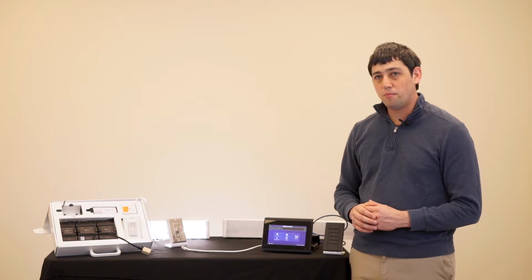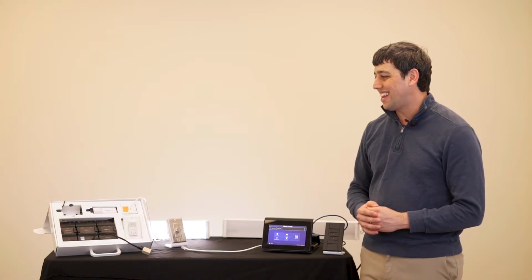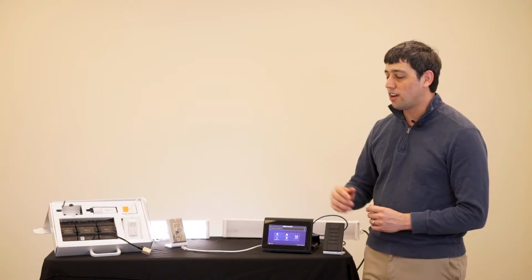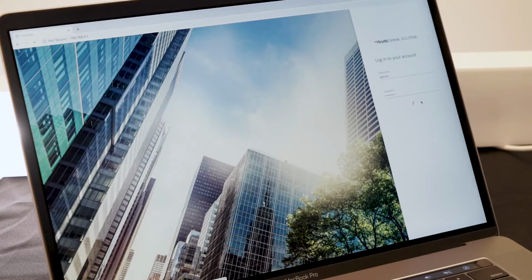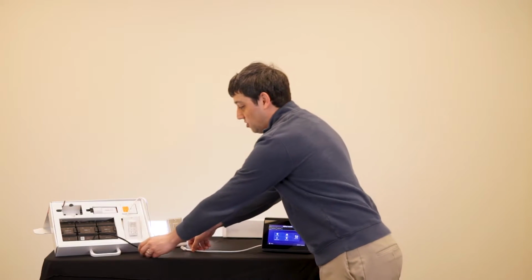Once that's set up, the one additional piece of information you need is the BACnet instance ID of your nECY. That can be found by logging on to the nECY admin console, going to the BACnet tab, and right there you can see the BACnet instance ID. In this case, it's 1007. With that information in hand, I can connect the two systems over Ethernet.